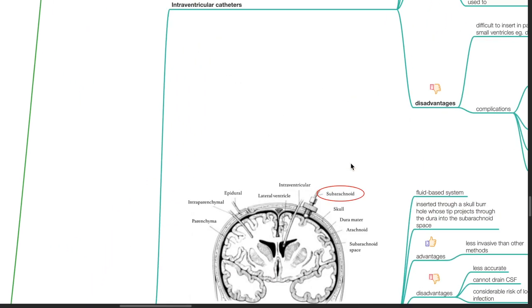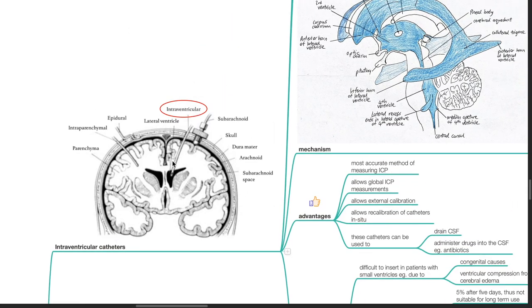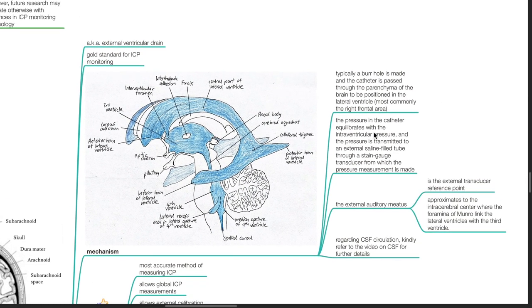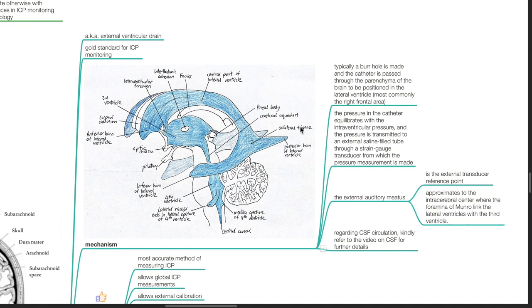Invasive methods. Intraventricular catheters, also known as external ventricular drain. It is the gold standard for ICP monitoring. Mechanism: Typically a burr hole is made and the catheter is passed through the parenchyma of the brain to be positioned in the lateral ventricle, most commonly the right frontal area. The pressure in the catheter equilibrates with the intraventricular pressure and is transmitted to an external saline-filled tube through a strain gauge transducer from which the pressure measurement is made. The external auditory meatus is the external transducer reference point. It approximates to the intracerebral center where the foramina of Monro link the lateral ventricles with the third ventricle. Regarding CSF circulation, refer to the video on CSF for further details.